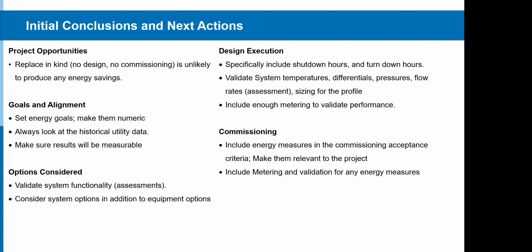During design, we try to consider options that actually make a difference. What we see very often is design engineers love to show you, hey, here's three different types of chillers: the Trane chiller, the Carrier chiller, and the York chiller, and then they do a life cycle cost analysis on that, and you go, well, that's crap. All of those are like 5% plus, very marginal differences.